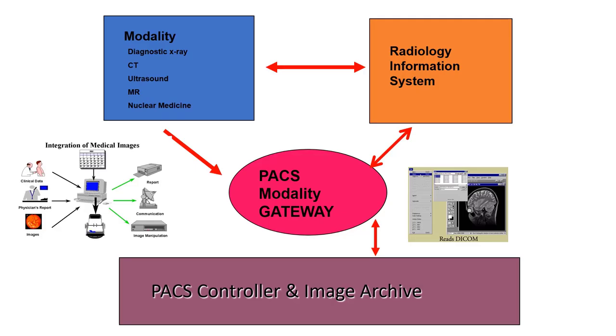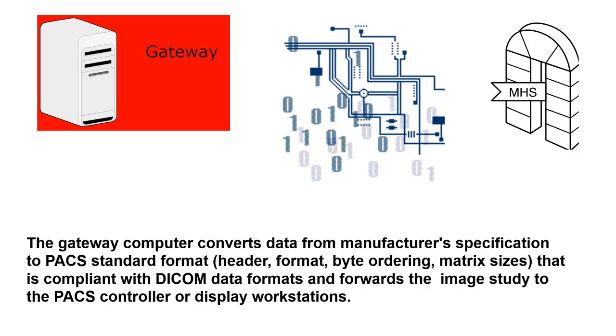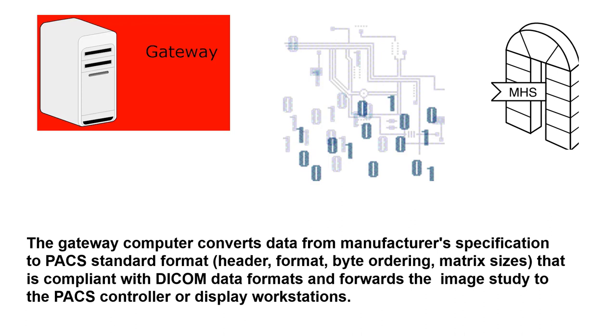We integrate medical images through the use of the PACS controller and image archiver. The gateway is a computer that converts data from manufacturer's specification to a PACS standard format that is compliant with DICOM data formats and forwards the image study to the PACS controller or display workstations.